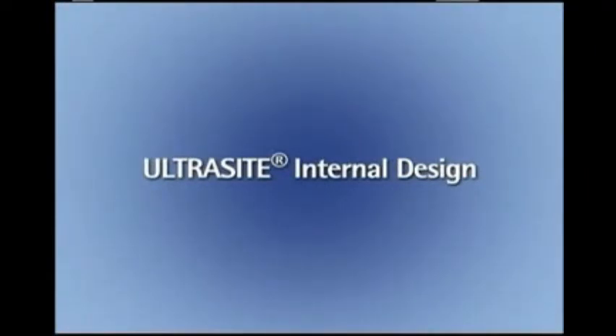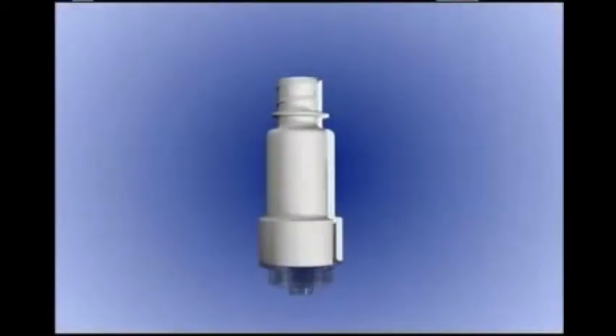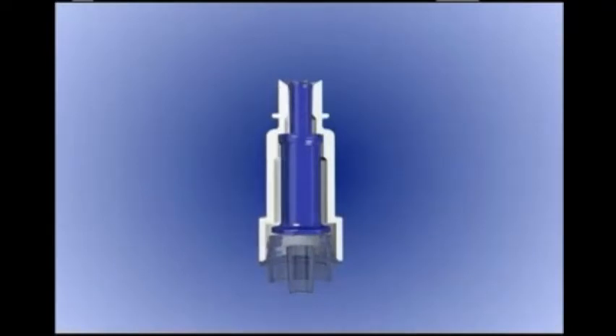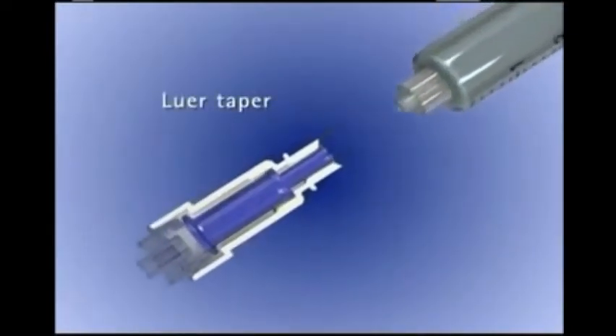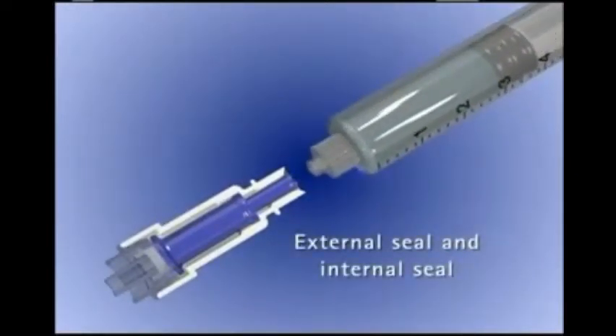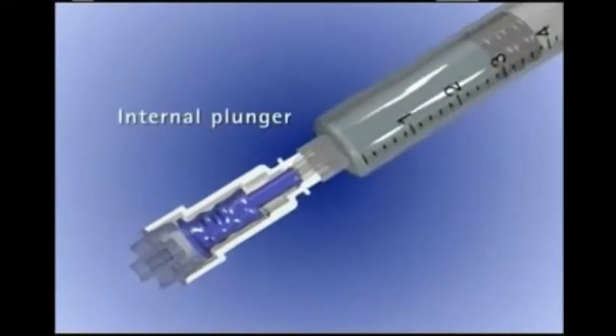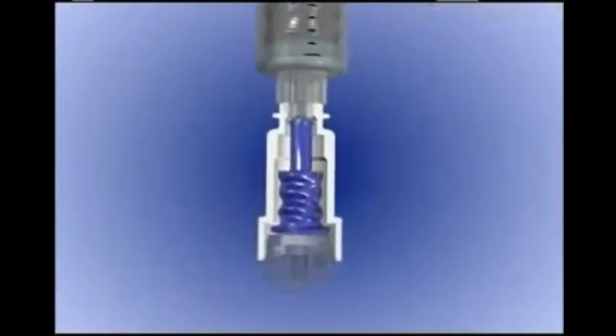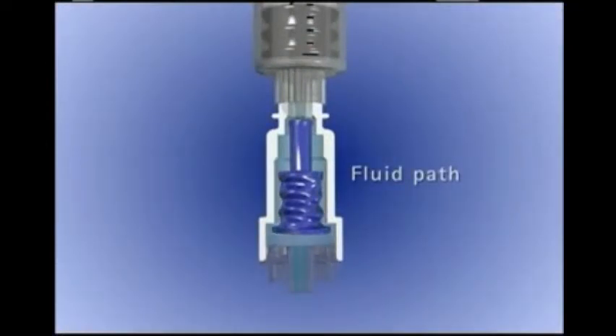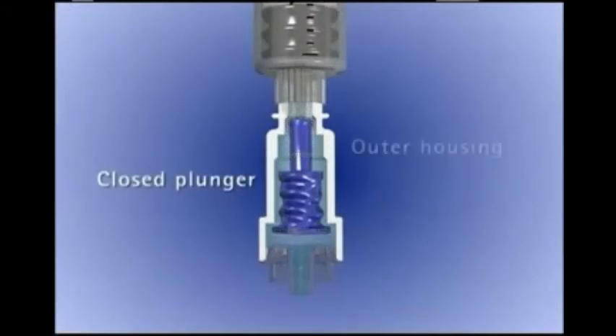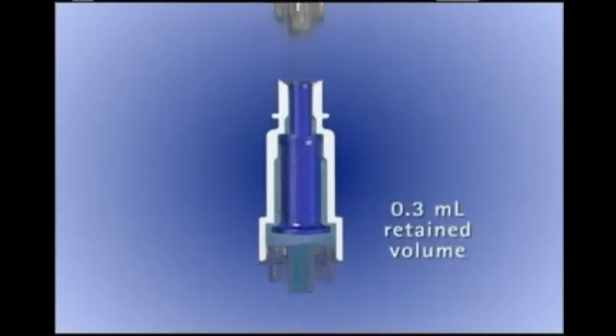Before continuing with the flush procedure, let's look at the internal design of the Ultrasite Luer access device. A view of the inner components and fluid flow tells an important story. Upon connection with a Luer lock syringe or IV tubing, the external seal and internal seal of Ultrasite open. Then, pressure on the internal plunger opens the flow path so fluid can flow through the device. This design allows the fluid to flow in an open, unrestricted way all around the entire closed plunger inside the outer housing. There are no hidden areas where fluid could accumulate and become trapped. The fluid volume retained by Ultrasite is only 0.3 milliliter. When the syringe or IV tubing is disconnected, Ultrasite automatically closes.